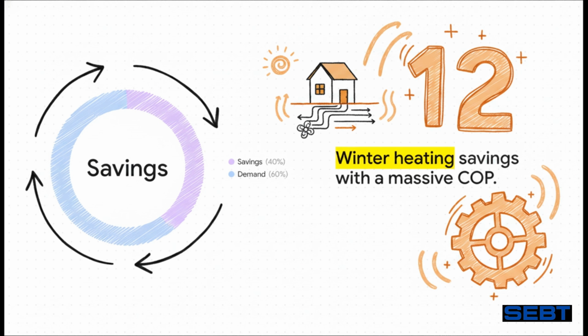Backing up the American data, there was a rigorous field study over in France by ADEME. They proved the system can operate with a COP, or coefficient of performance, of around 12. In really simple terms, for every 1 unit of electrical energy spent running the fans to move the air, you get 12 units of thermal energy back. That yields a massive 40% reduction in mechanical heating demands during the winter.